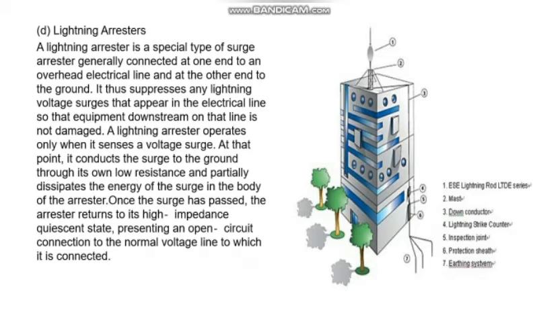At that point, it conducts the surge to the ground through its own low resistance and partially dissipates the energy of the surge in the body of the arrestor. Once the surge has passed, the arrestor returns to its high impedance quiescent state, presenting an open circuit connection to the normal voltage line to which it is connected.